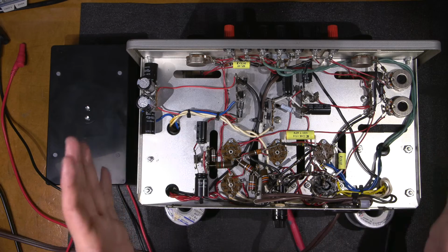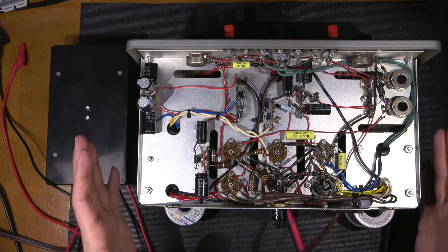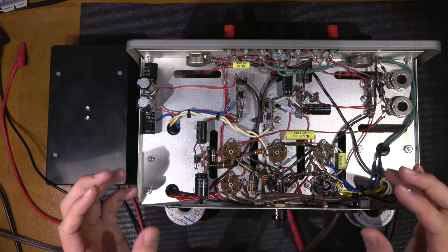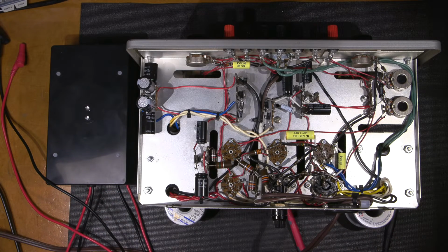Even if the vacuum tubes are coming into emission, and they are into emission for a long period of time, you shut it off and the tubes are cooling down, you still want to go through and check those caps. Definitely do not take any chances whatsoever. Any piece of gear that has high voltage in it, you want to test.